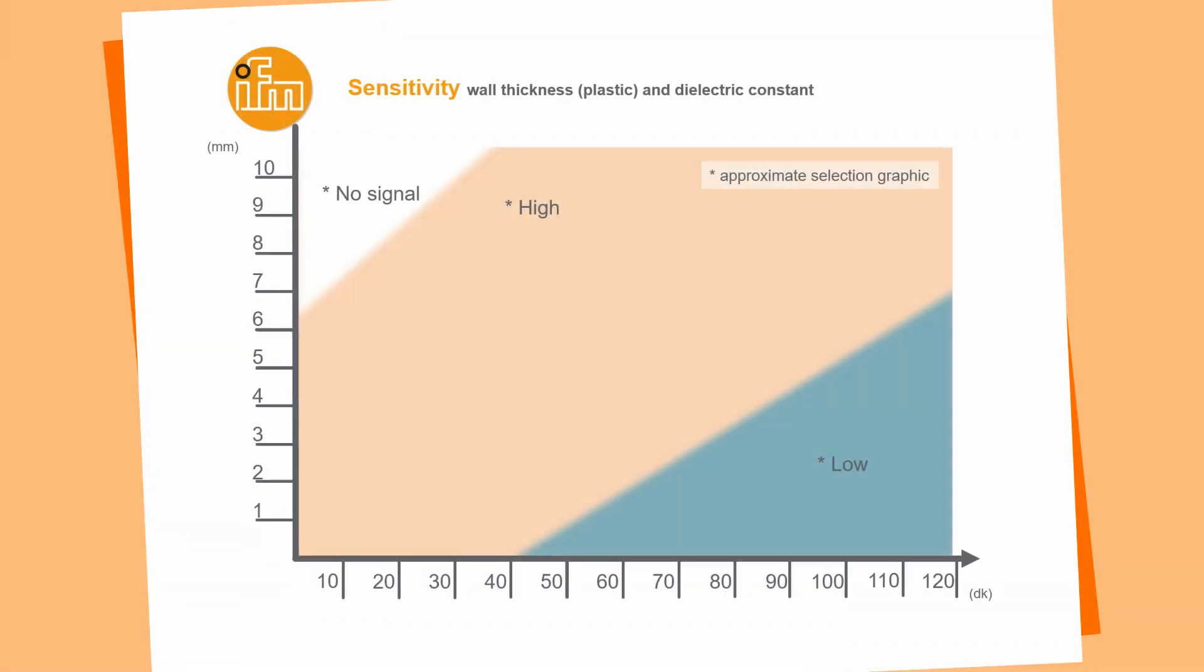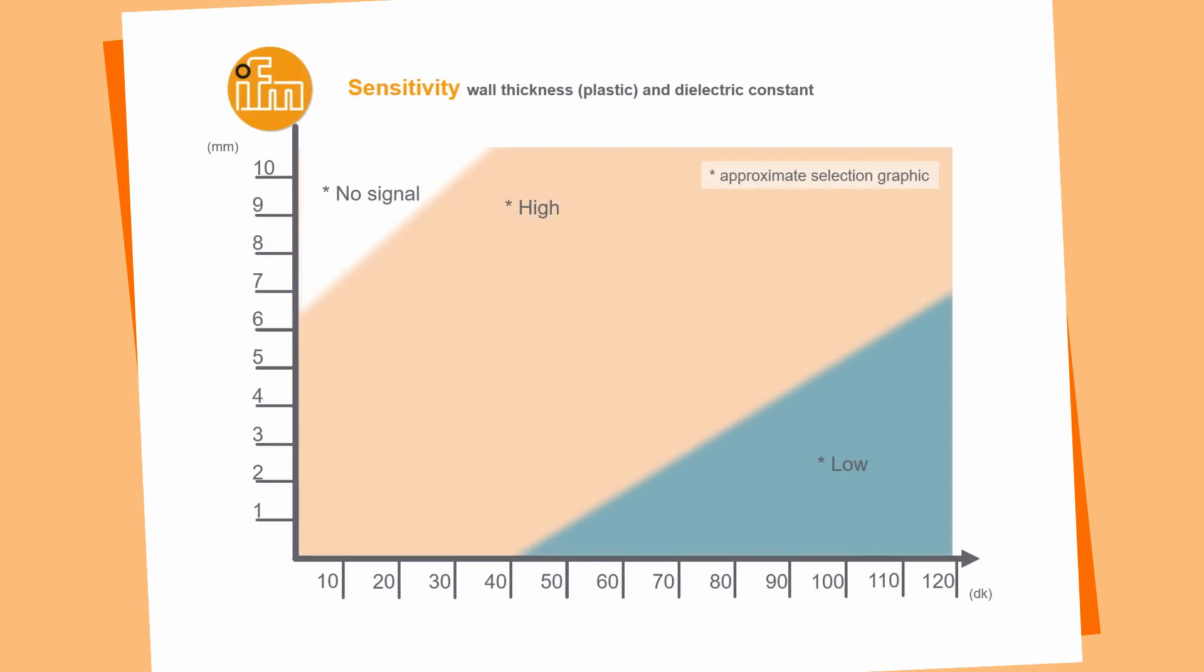You can see in this graph where the sensitivity high or low is the best. On the upper left side you see the wall thickness of 10, 9, 8, 7 millimeters and on the bottom you see the dielectric constant. So with a dielectric constant of 10 which is quite low and a wall thickness of 10 which is very high we are not able to detect any liquid or grain or whatever. On the yellow part you see that the perfect setting of the sensor is the sensitivity high and when you have a very high conductive media for example acid which is higher than 120 DK and a very thin wall thickness it's good to use a sensor setting sensitivity low.